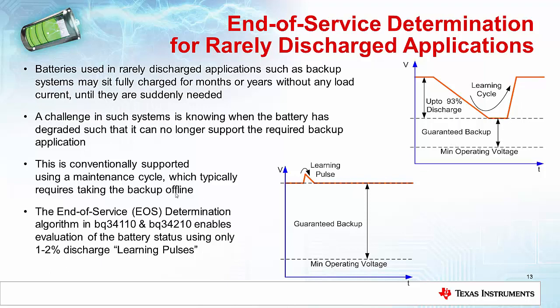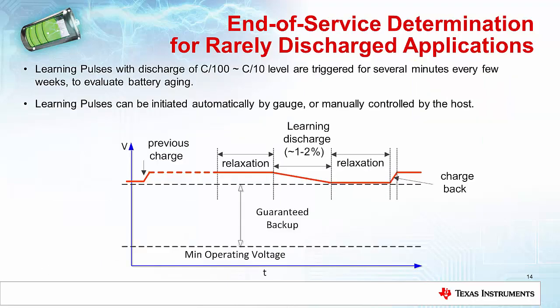So what we've developed is a new algorithm called end of service determination, which we've rolled into a few of our newer parts. This lets us evaluate the health of the battery by only doing very small learning pulses that discharge the battery a very small amount, and can keep the system completely online while it's functioning. We run these learning pulses. We basically turn on a controlled discharge somewhere in the C/100 to C/10 level. We trigger that for just a few minutes to evaluate the transient of the battery.